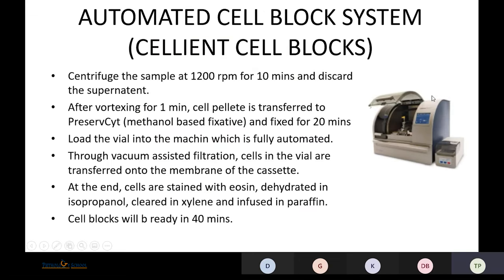Coming to the automated cell block system — Cellient cell blocks — we centrifuge the sample for 10 minutes, discard the supernatant, then after vortexing for one minute, the cell pellet is transferred to a PreservCyt (methanol-based fixative) and fixed for 20 minutes. The vial is then loaded into a fully automated machine. Through vacuum-assisted filtration, cells in the vial are transferred onto a membrane in the cassette. Cells are then stained with eosin, dehydrated in isopropanol, cleared in xylene, infused in paraffin, and the cell block is ready in 40 minutes.